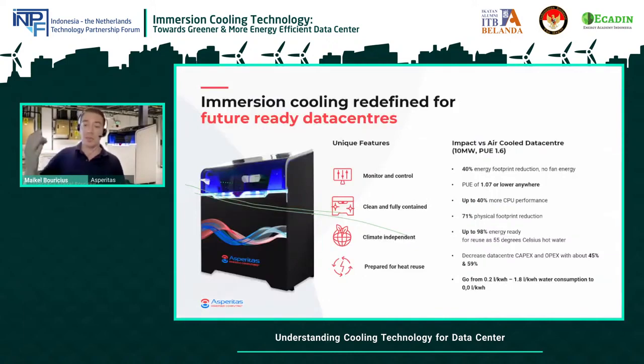Looking more at the data center facility side, there's always impact there as well. I made a comparison just for this session, compared with an air-cooled 10 megawatt data center, which is maybe a bit below average, but a nice module to use, with a PUE of 1.6 — and I heard that's also a bit low compared to the regional average. But you can see, even at a PUE of 1.6, we have a great energy footprint reduction, almost 40%, mostly because we don't need that much power for cooling anymore, both in the server and in the facility.